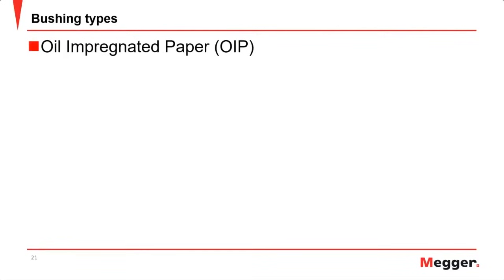This is your typical kraft paper, and that is then filled with mineral oil. And the paper is a good insulator, but it is not perfect. There are tiny voids in paper, and so the oil is used to help fill in those voids. The oil is also used to help with convection cooling within a transformer. But when we talk about bushings, not a lot of convection going on, so really that oil is used to fill in the gaps of that kraft paper to make the best insulation system that we can have.